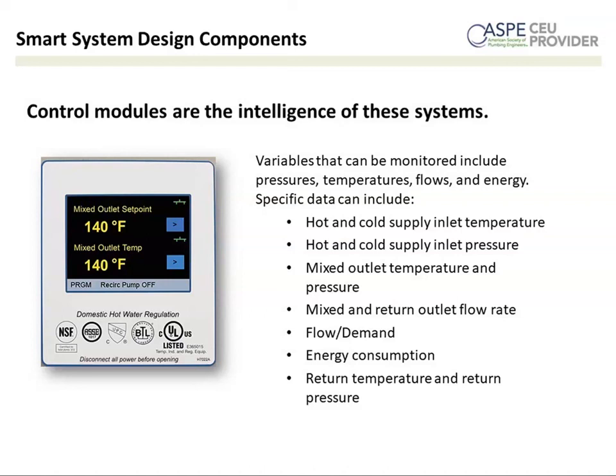Setting your high temperature alerts and your low temperature alerts can be done from here. In most cases, and in this one in particular, it's password protected, so you just can't get into the system. In this case, those little blue buttons to the right allow you to scroll through data if you want a quick look to see what's going on in the system. By hitting the blue buttons, you can see your hot and cold inlet temperatures, your pressures, your mixed outlet, your flow, and energy consumption. That you can do without a password.